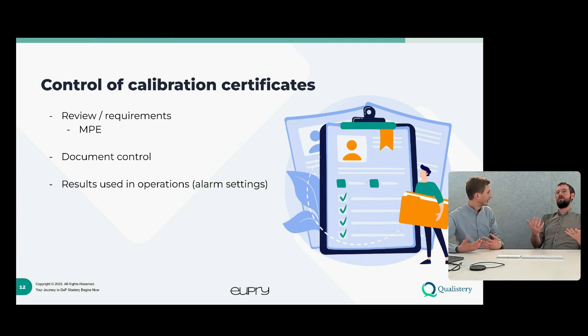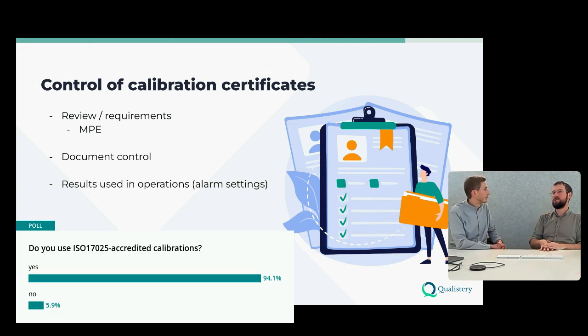I think one of the key elements to why having control over calibration certificates and having them easily reviewable during an audit matters is because my personal theory is that during an audit it's such an easy thing to check. It doesn't require a very deep understanding of the process requirements. It's fairly easy to ask, is there a calibration certificate, and have you understood what's in it?